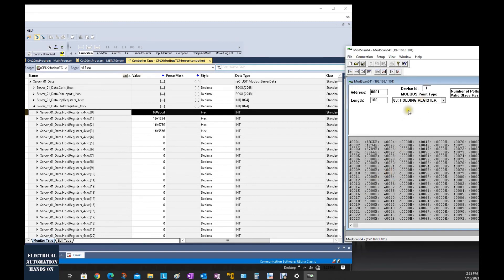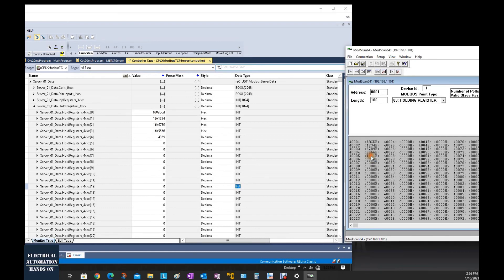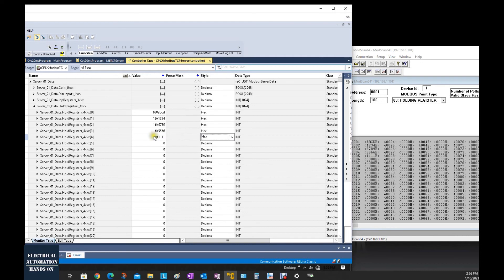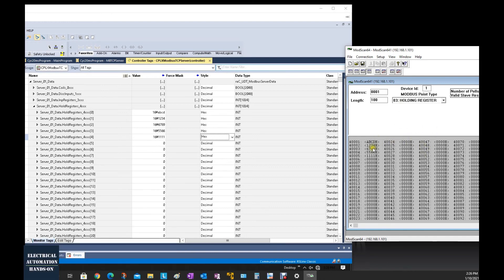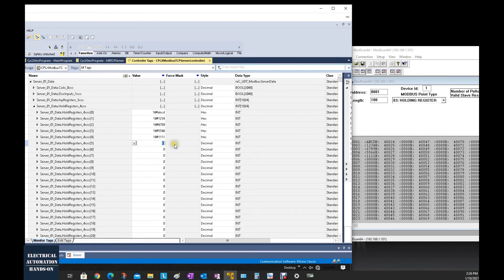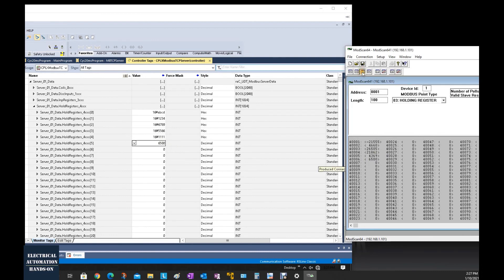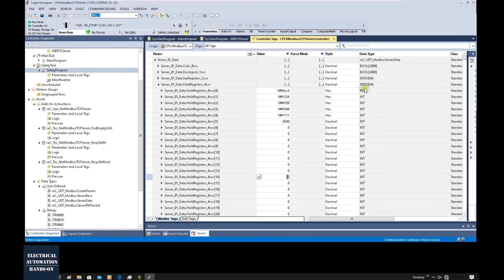From the client side, because this is software, once we switch to function code 03, the sending and receiving share the same Modbus address. That's why when we send data, it also reads back. If we are using a PLC as a client to send or read data, when you switch between function codes 03 or 16, this software handles it automatically. If we test with an integer — for example, 6,500 — and switch to decimal mode, we can see 6,500 is received correctly, just with the one-address offset starting from zero. This is the CompactLogix Modbus TCP server function.